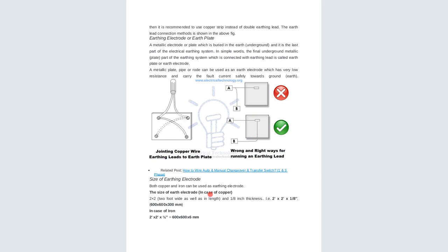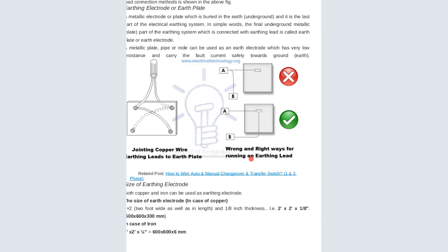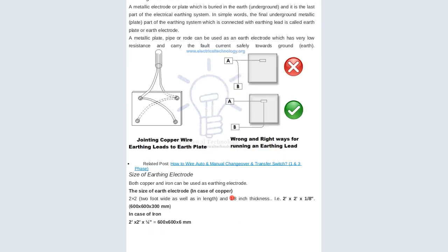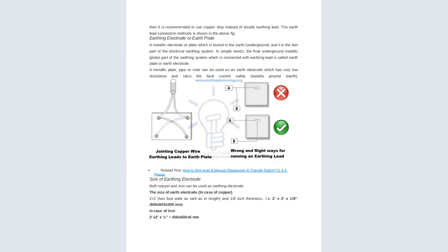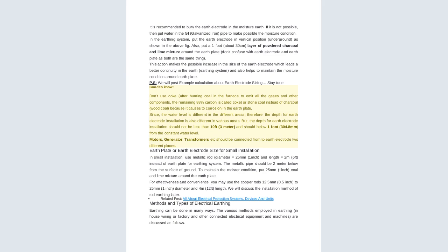The size of an earthing electrode: both copper and iron can be used for an earthing electrode. Now the size of the electrode in the case of copper is 2 times 2, that is 2 feet by 2 feet. And these calculations, when we come back to school, we will see them in the workshop and do it practically, how we do the earthing.